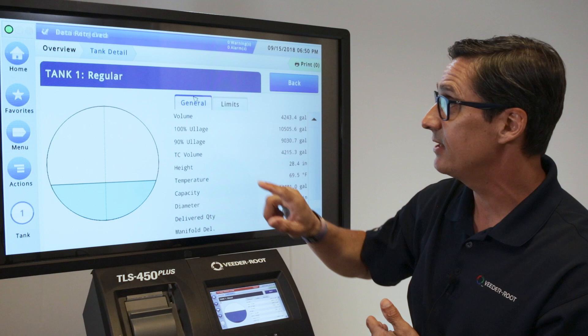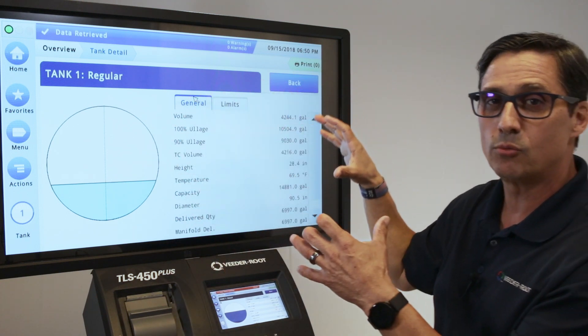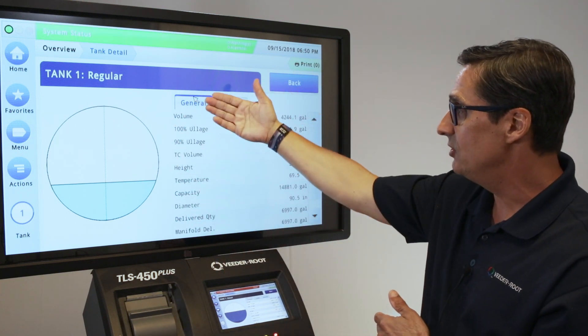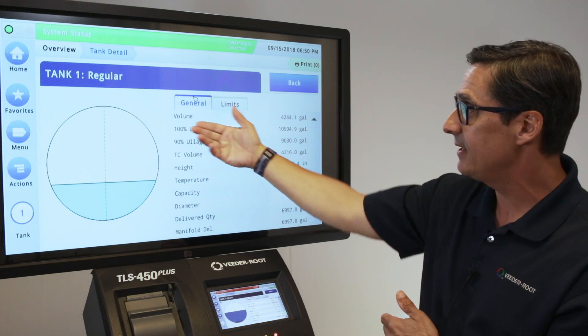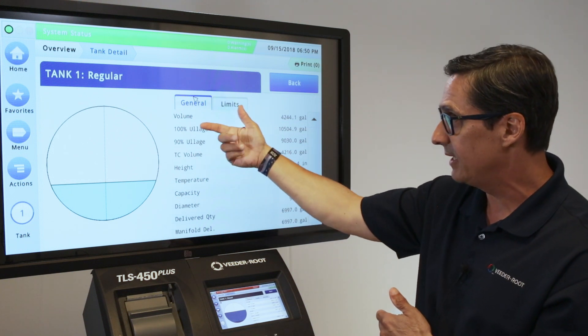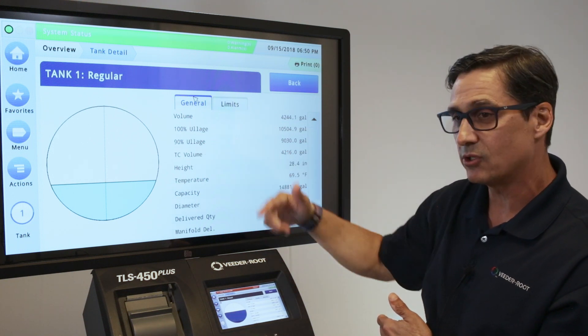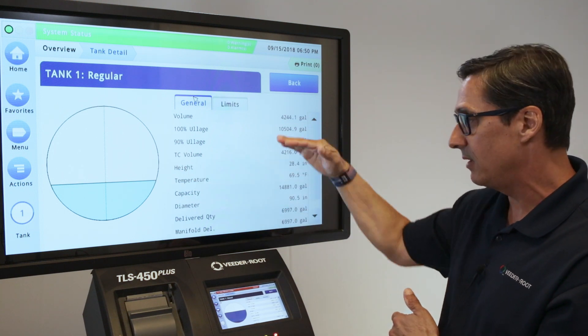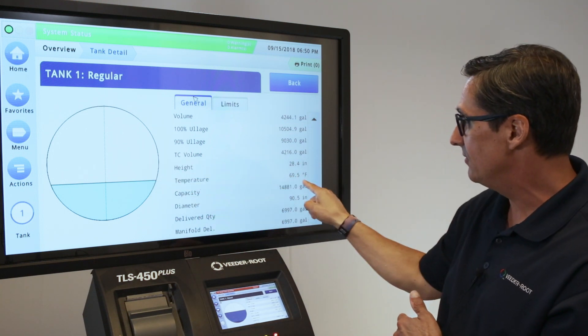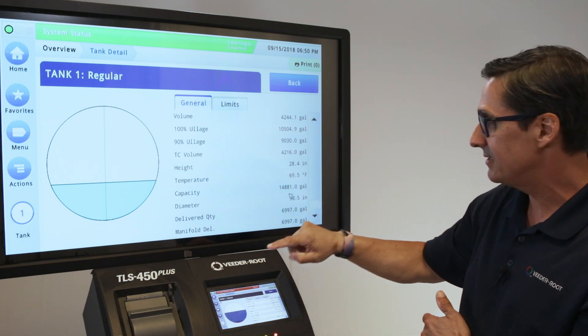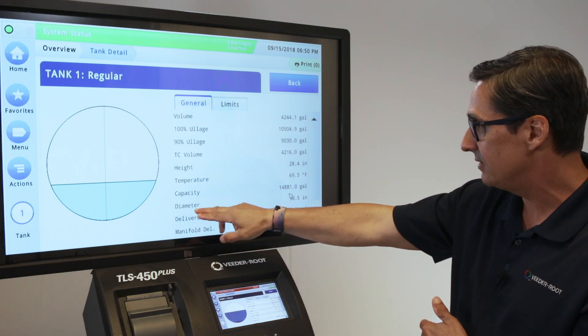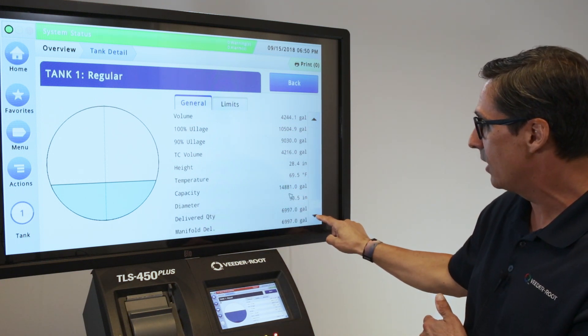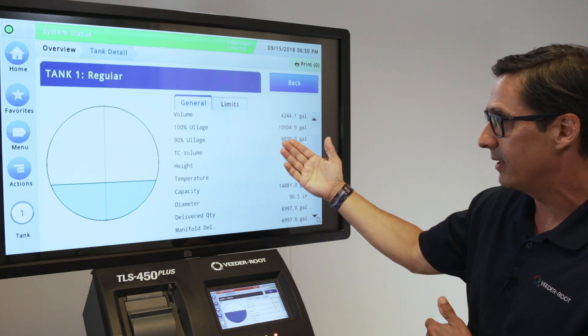If I click on this arrow button, it gives you a superimposed detail of that tank. It gives you the general information of what's going on in the tank: volume, ullage, temperature-compensated volume, the height in the tank in inches, temperature, the capacity of the tank, the diameter, and then delivery quantities and manifold delivery quantities.